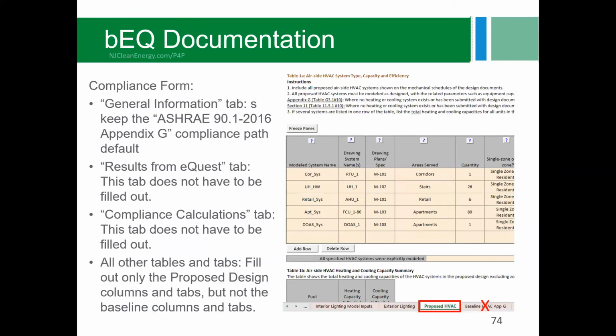The bEQ documentation is actually a little simpler than Appendix G. In the compliance form on the general information tab, keep the default that says ASHRAE 90.1 2016 Appendix G. Just leave the default. You don't have to fill out the results from eQuest tab, or the compliance calculations tab. For all other tables and tabs, all you have to fill out is the proposed design information. You do not need to fill out baseline information. So you can skip a whole tab for HVAC, as shown here. Baseline is crossed out, it's not applicable. You just fill out the proposed information in the compliance form.